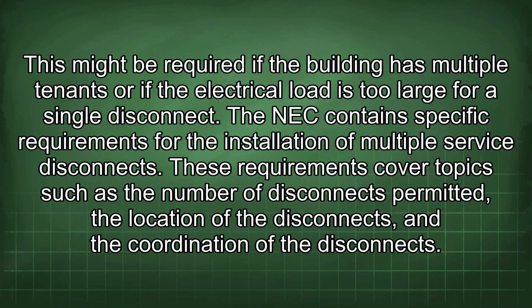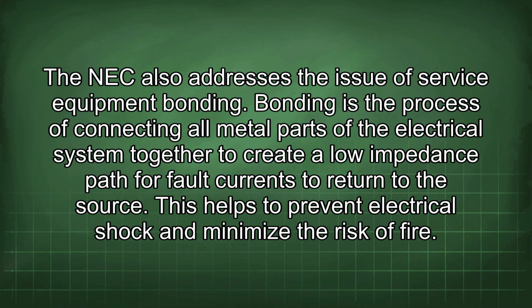the disconnects. The NEC also addresses the issue of service equipment bonding. Bonding is the process of connecting all metal parts of the electrical system together to create a low impedance path for fault currents to return to the source. This helps to prevent electrical shock and minimize the risk of fire.